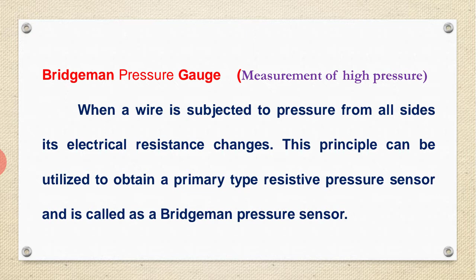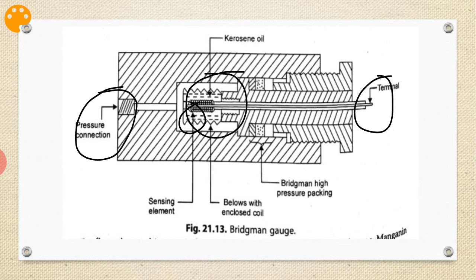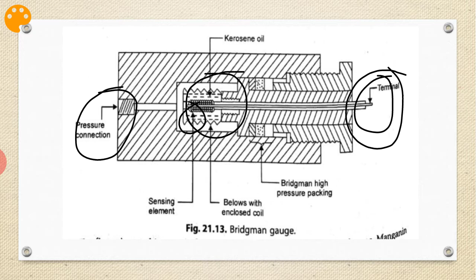This is the figure which shows a Bridgman gauge and how it is implemented. Here is the sensing element, the pressure connection is connected here, and this is the terminal where the resistance element leads are taken out. The sensing element does not actually contact the process medium but is separated from it by a kerosene-filled bellows. One end of the sensing coil is connected to the central terminal while the other is grounded, thereby completing the necessary electrical circuit. So this is the basic principle involved.